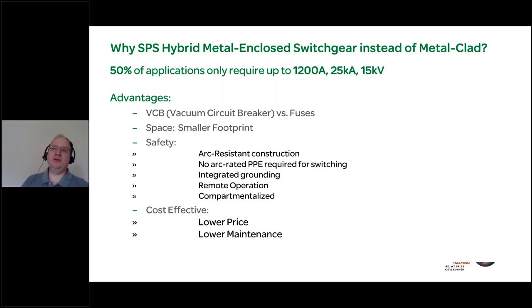And what I mean by hybrid is, I want to be clear, this is built to a metal enclosed standard. So it is metal enclosed switchgear, but this switchgear contains elements of metal clad functionality, such as the option for draw out circuit breakers, compartmentalization, metal clad style bus ferrules, and other features that you would normally only find in a metal clad environment.